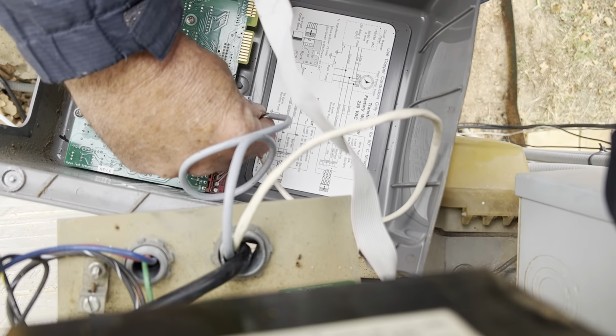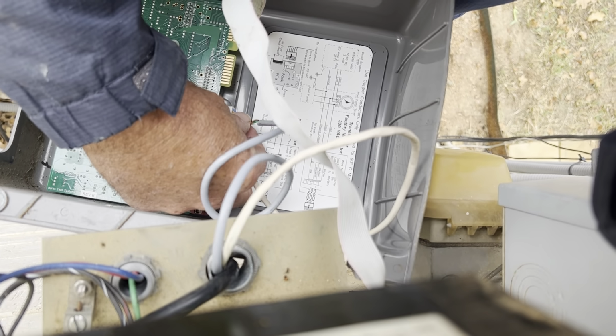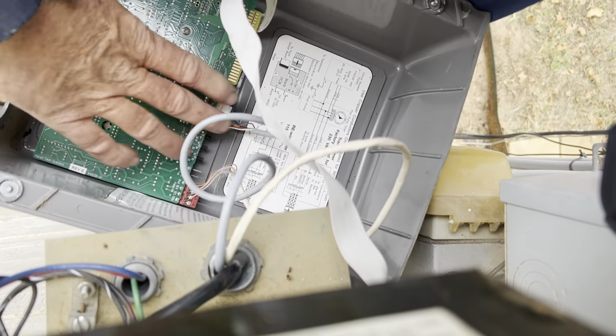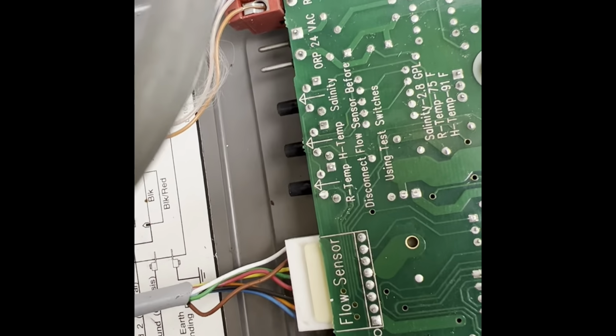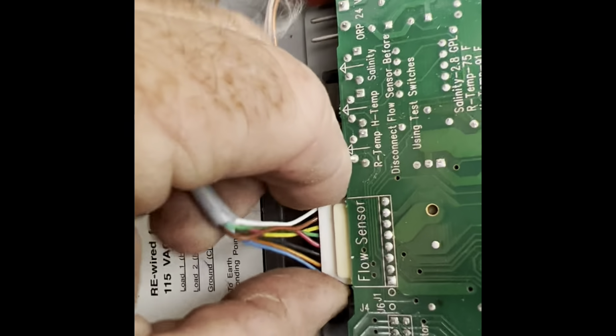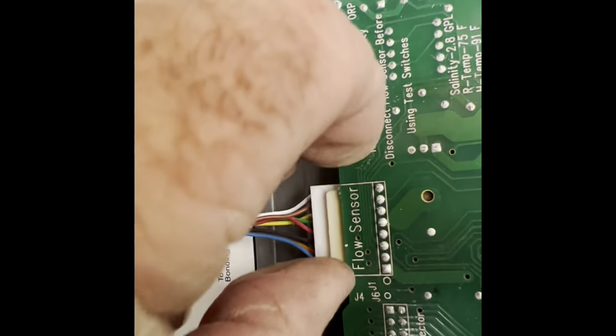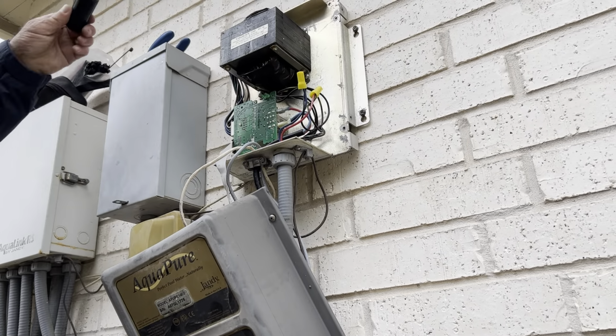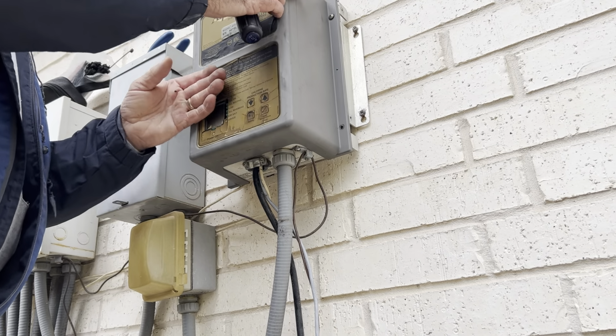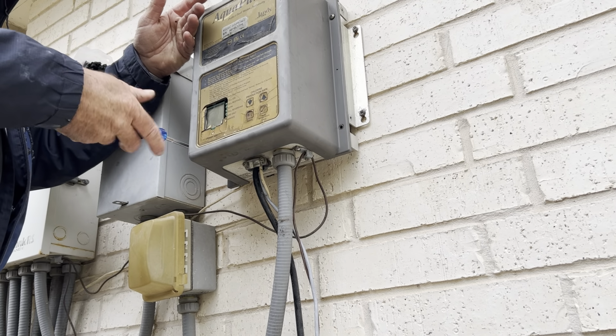Okay, this will be the final connection. Connect the tri-sensor wire to its port, snap it in good. You can see it labeled here, flow sensor. It says flow sensor, but it's actually the tri-sensor, has flow, temperature, and salt, all reading on the same sensor. And we'll get the box put back on the wall.